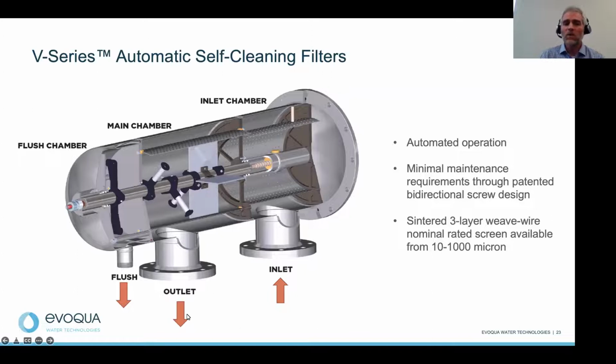Quite simple. What really is the magic about this filter is how it cleans itself. Again, no moving parts, no external electric motors, pistons, technology, right? No limit switches to make sure you're cleaning effectively or it's operating performantly. We're using inlet water pressure to ultimately act as the force to clean itself. So over time, solids are collected on that internal inlet, that fine screen. Over time, pressure will build at a DP of approximately 7 psi. It will trigger a controlled flush valve.